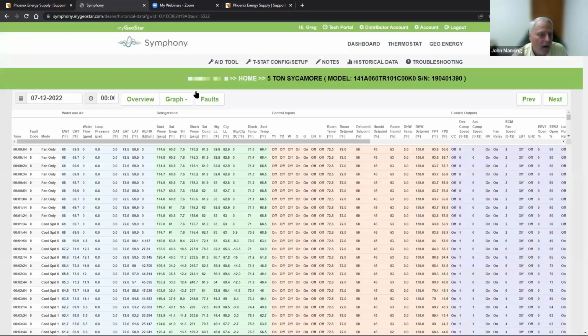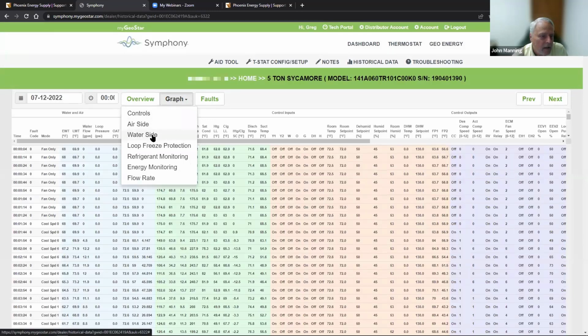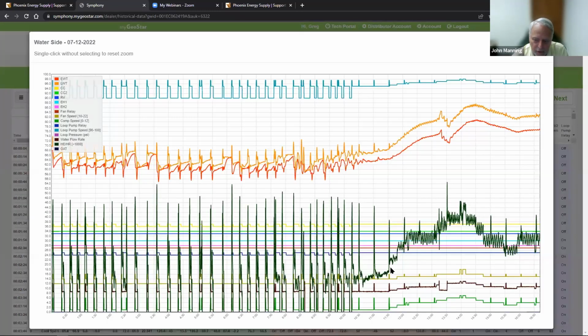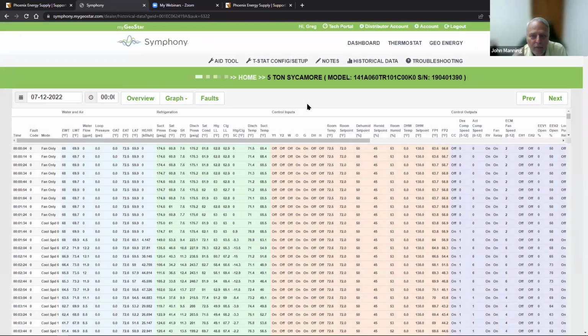And if I can close that, other charts we may want to take a quick look at is water side. And this one's a little busy, but this illustrates the flow rate. This is one curve we look at. The delta T in the water. So entering and leaving water temperatures. You can see during the night when it wasn't running constantly, the delta T's and entering water temperatures are very mild. So you can expect some very good efficiencies. During the day, we're running more consistently at a higher speed. Our delta T's and entering water temperatures have risen to accommodate that change in load. So it's a powerful tool.